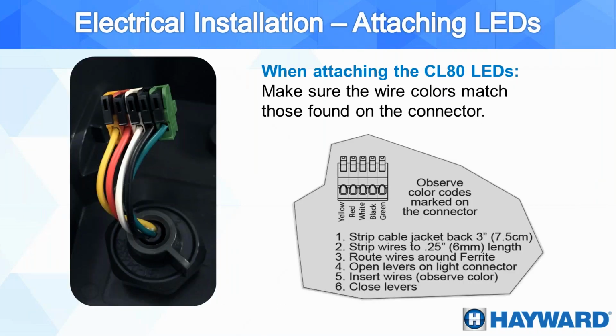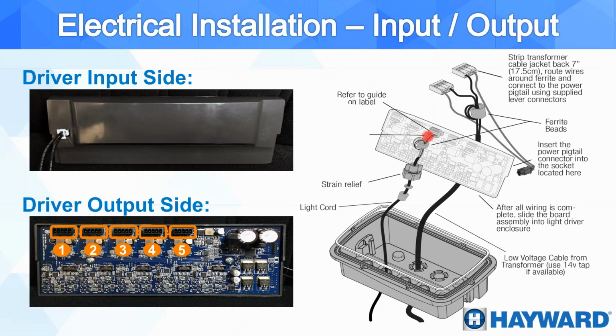And then I want to show you how the plug looks, because it is color coded. These lights, instead of having the standard 2 wires, the ColorLogic 80 has a 5-wire cable. But each of those 5 wires is color coded. So when we are assembling our plug in order to connect into our board here, they are color coded. So it makes it very easy. Obviously, we have the yellow, red, white, black, and green, and each of those is going to go to the same color on the plug. So it makes it a lot easier to just wire it and then come in and plug it directly into the board. So installation is very simple. It is nothing complicated around it.